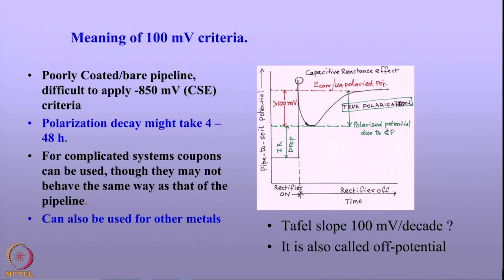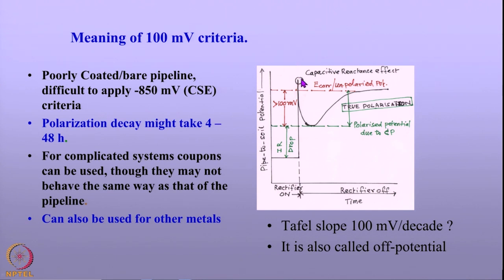There is yet another criterion: the 100 millivolt criterion. This becomes very important when pipelines are poorly coated or when dealing with bare pipelines, because using the 0.85 volt criterion on bare pipelines requires much more current, making it unviable. In this criterion, you turn off the rectifier and follow the potential; there may be a spike due to capacitive reactance or inductance, followed by a drop in potential.